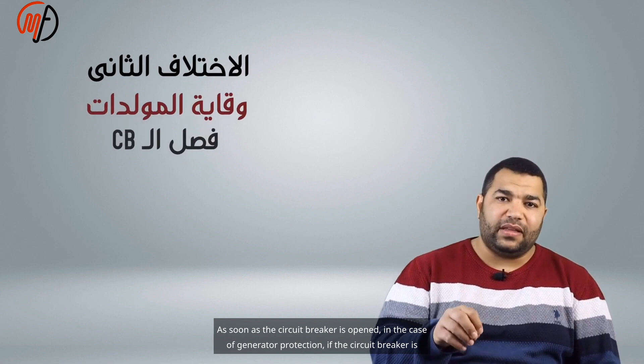This is contrary to the protection of all other elements in the network, which are secured and isolated at the moment of the fault, as soon as the circuit breaker is opened. In the case of generator protection, if the circuit breaker is tripped, the turbine must also be disconnected at the same time, and an emergency shutdown for the exciter must be performed. Otherwise, the fault will continue to be fed from the generator's windings that are still spinning and generating electricity.